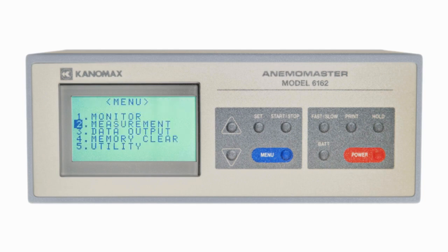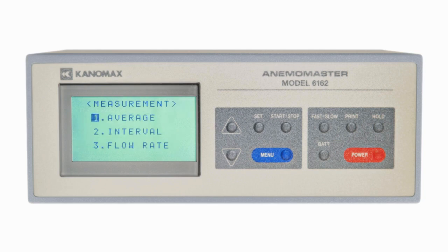There are 3 modes you can use to take measurements with your anemometer. Average mode averages all data from the duration of the measurement. Interval mode averages data within multiple intervals and then presents each interval's average at the end of the reading. Flow rate mode calculates air volume using average air velocity and the area of the duct you're measuring.